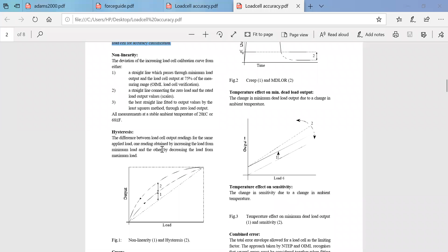And one more parameter you have to understand is non-linearity, which comes into the picture while measuring with the load cell. Usually you get deviations when you use a load cell. It depends upon how well it is calibrated also. Without calibration, you cannot use a load cell because it won't yield a proper reading.